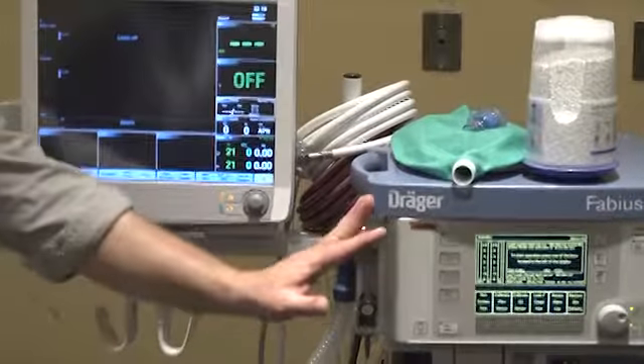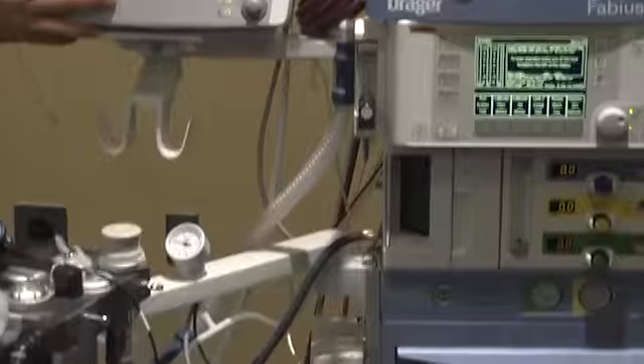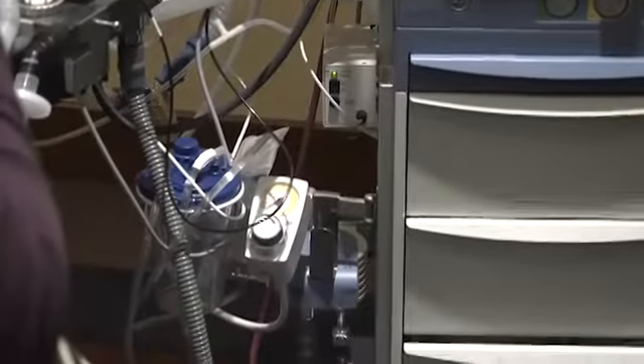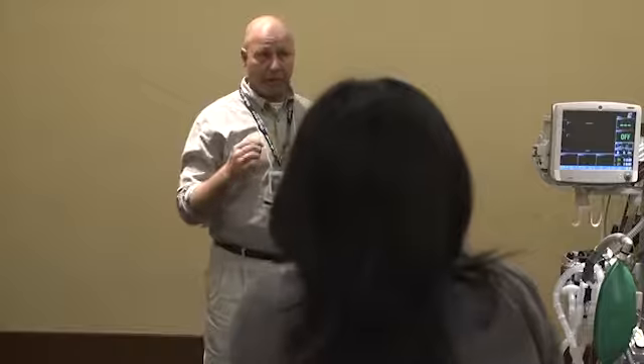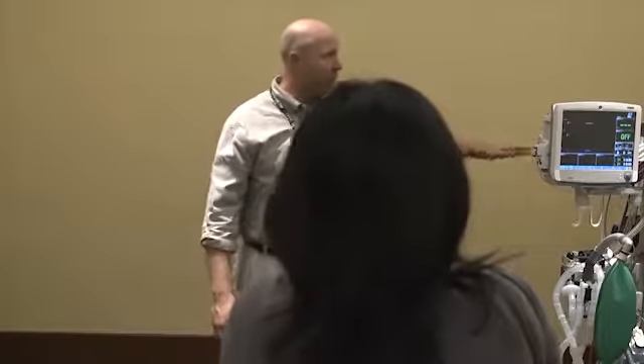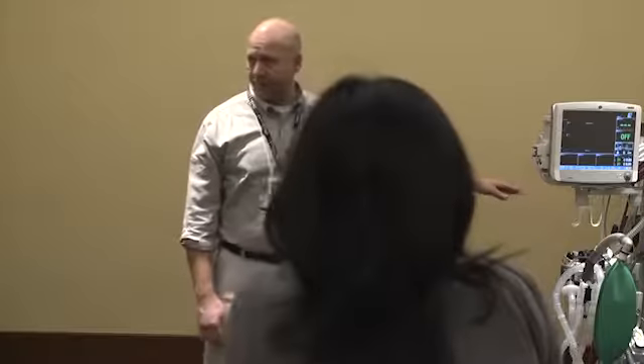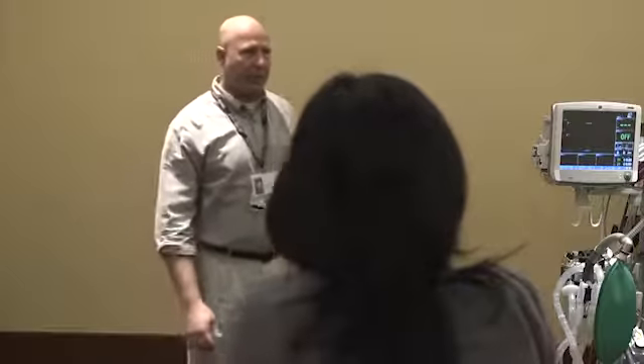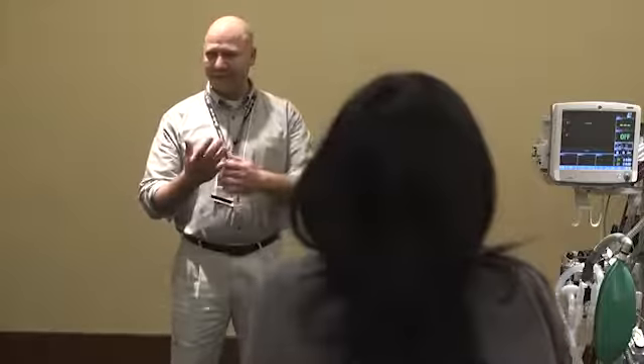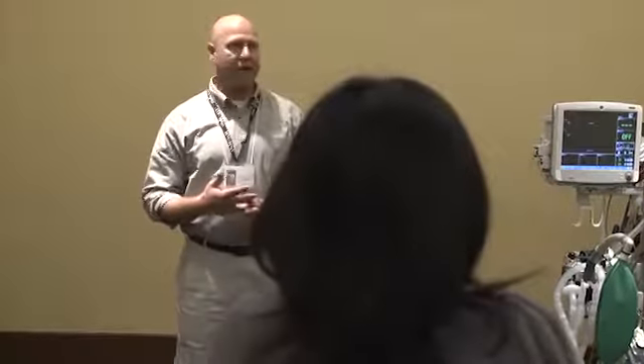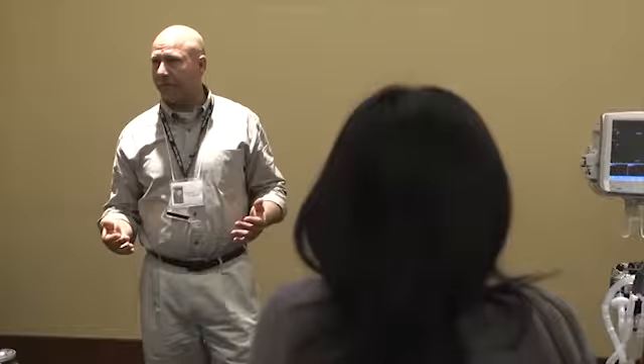Now, that being done, y'all are the last defense against hypoxia. The oxygen ratio controller, that proportioning device, has a specification of 21 to 28% on the Narkomed, and actually runs 21 to 34% on the newer machines. Now, all electronics and all mechanics always have a 5 to 10% acceptable tolerance. So what if the oxygen ratio controller is in that 5%, the O2 sensor is in that 5%, your medical gas is in that 5%? We start getting 5% here and there. When we're dealing with 2-3 percentage points, you can get to a dangerous level if everything's going south. So that's where y'all come in.